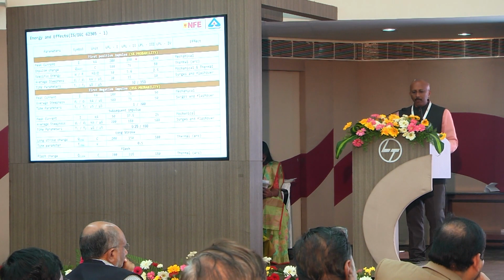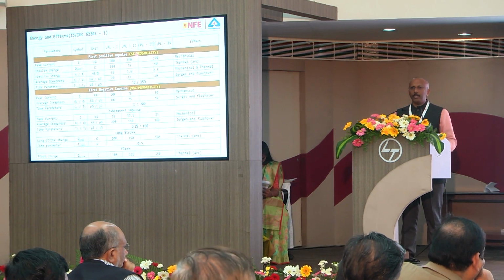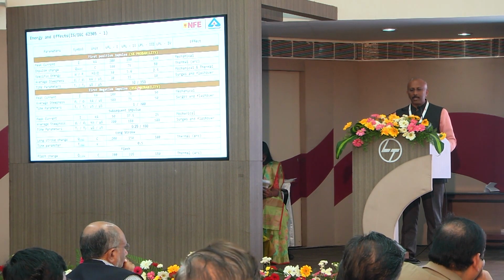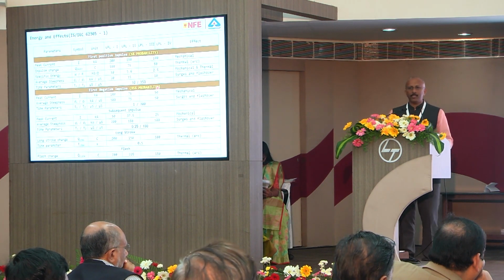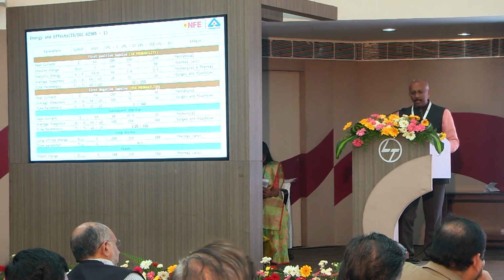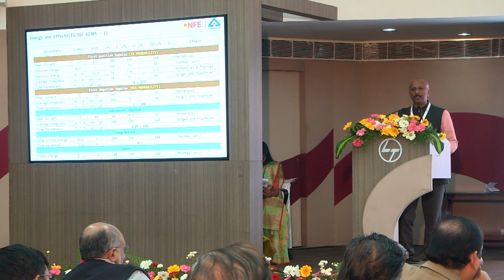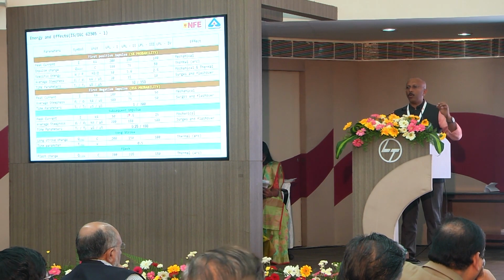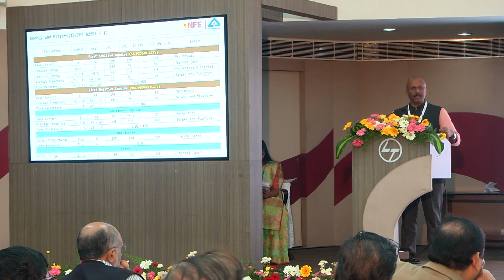But what is important for you is that positive impulse and negative impulses are there. Positive impulse, the maximum is about 5%, negative impulse, it can come up to 95%. Out of 100 lightning strikes, 5 can be positive and 95 negative. Then there are other chances as well, subsequent impulses. That means in a stroke, first there is an impulse followed by several impulses or several strikes.